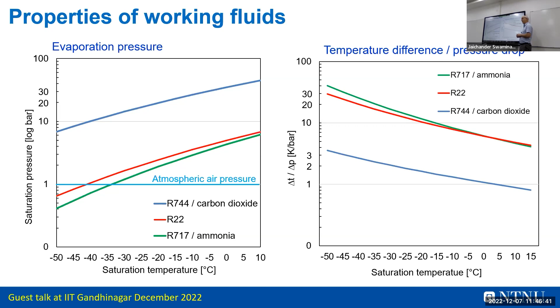And at -50, if we have 1 bar pressure drop, we lose only 3 Kelvin in the evaporator. 1 bar is a lot. Compared to the other fluids, you see it would be 30 Kelvin difference in the evaporator. But this value is quite low. At around 5 or 0 degrees again, 1 bar is 1 Kelvin, which means we can allow much larger velocities in evaporators and so on, very high heat transfer, even not penalizing too much on the temperature glide because of the properties. So that's good, because in other systems, we can see 10 Kelvin temperature difference or 5 Kelvin difference if the heat exchanger is huge, because of the pressure drop and the properties of the fluid. Now with CO2, it gets very uniform.